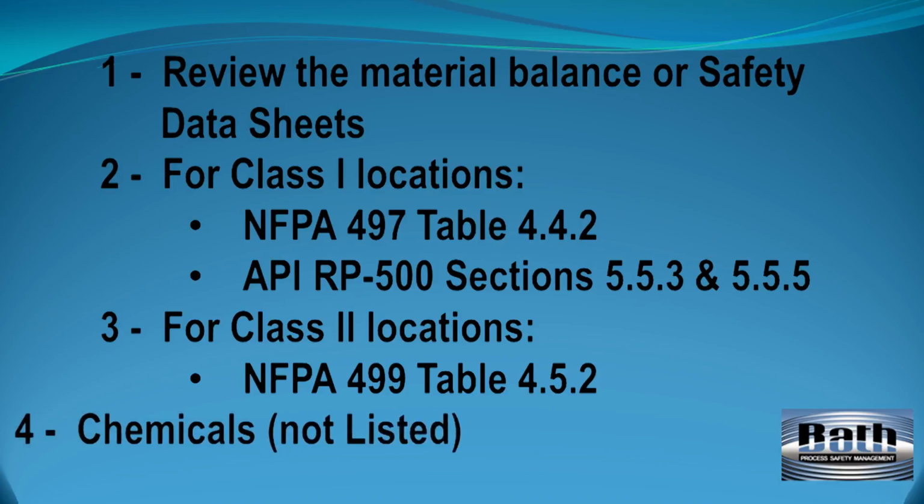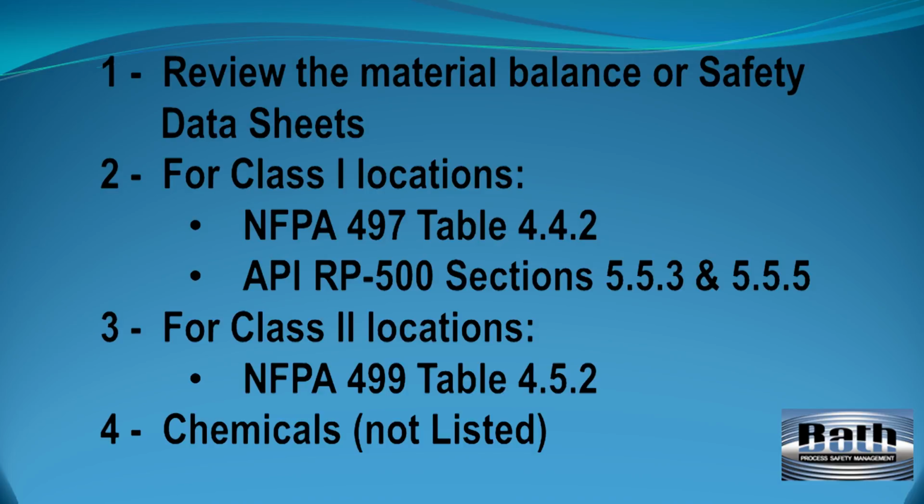4. If a chemical is not listed in either NFPA 497 or NFPA 499, then testing may be required to determine the suitability of electrical equipment in the locations under consideration. The importance of determining the correct material group cannot be overstated.